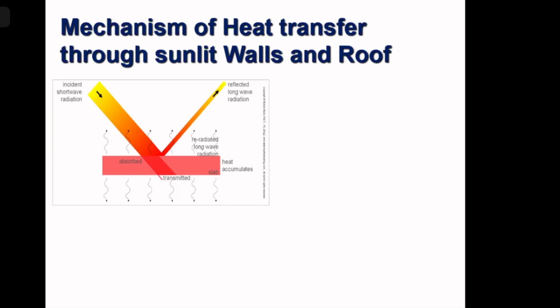So then delta T is not that big. The sun has gone down, the outside temperature has fallen, but the walls are still hot and will keep radiating heat inside. So the heat load will come in. Again, in the morning hours, the walls have become cool. Outside has become cold, but the outside wall takes a little time to get heated up. So in the morning hours, though delta T is low, the heat coming inside the room will not be that big, because the walls are still a little cold. Throughout the year, through the seasonal change, throughout the day, this will happen. So it's slightly complicated. So what will be the heat load? Next.